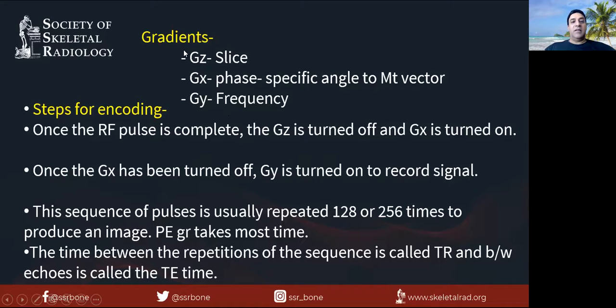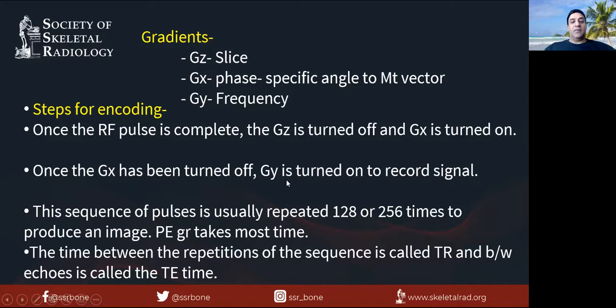When the signals come back, they have to be encoded — where are they coming from in space? By slice, phase, and frequency encoding. Once the RF pulse is complete, the slice-selecting gradient is turned off, the phase encoding gradient is applied to provide a different phase shift to the proton being encoded, and then the readout gradient is turned on to record the signal. This is repeated multiple times until the image is created — for a matrix of 256, you repeat 256 times.